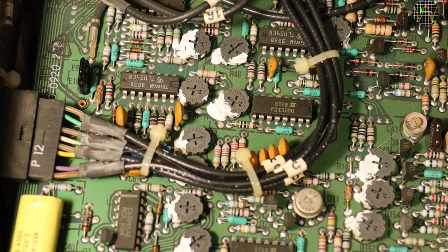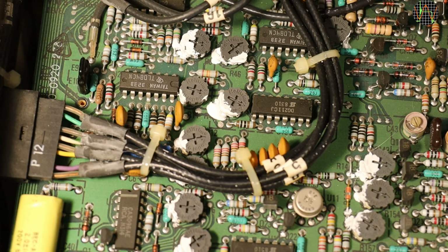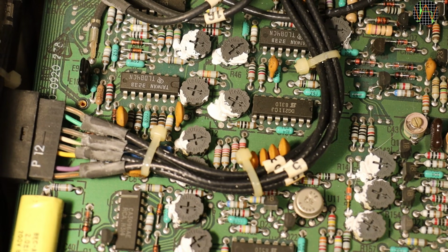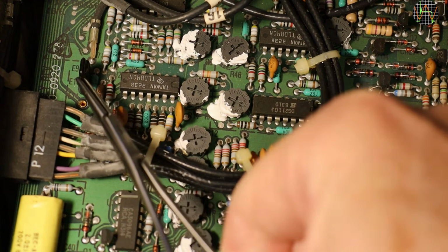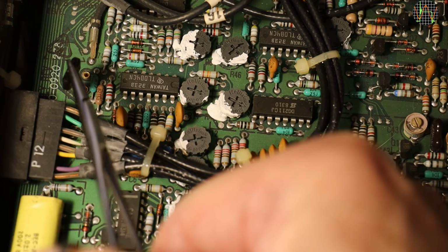And what do you know, that jumper is still in the position for calibrating the generator without synthesizer by connecting E9 with E10, when it should be in the position connecting E10 with 11 for operation or cal of the generator with the synthesizer. I have never come across this type of jumper where the pins are part of the jumper and the board contains sockets. It is obviously designed so it will never fall out by itself because it's stuck pretty good.